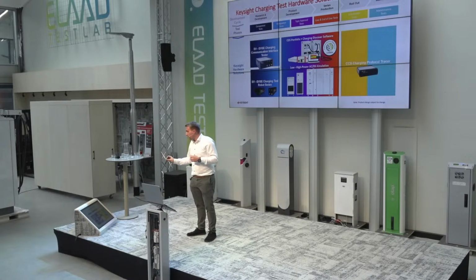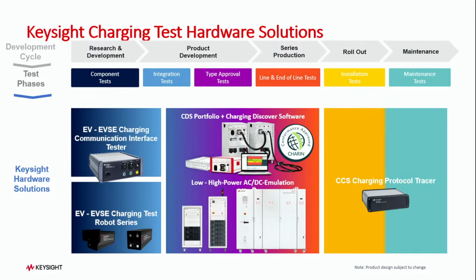On the lower side of the picture, you see that we also provide emulators, starting at low increments from 5 kilowatts up to 300 kilowatts per cabinet, which can be switched in parallel up to the megawatt level. We're perfectly prepared, and we're basically the only vendor on the market that controls the whole test system from its own portfolio.